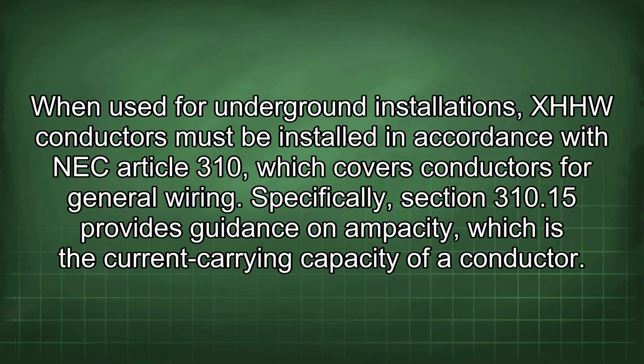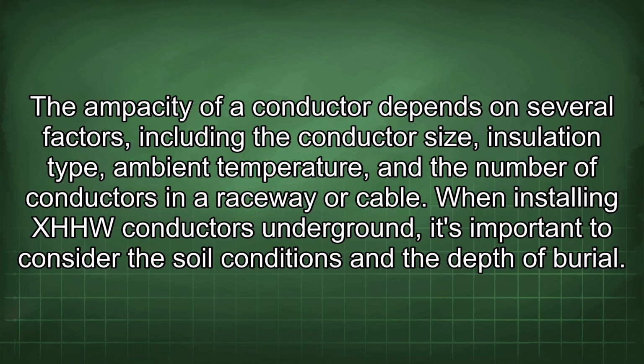When used for underground installations, XHHW conductors must be installed in accordance with NEC Article 310, which covers conductors for general wiring. Specifically, Section 310.15 provides guidance on ampacity, which is the current carrying capacity of a conductor. The ampacity of a conductor depends on several factors, including the conductor size, insulation type, ambient temperature, and the number of conductors in a raceway or cable.